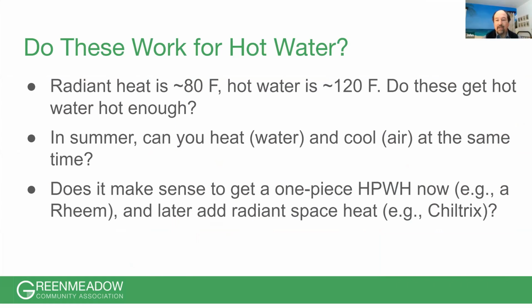Okay, yeah, so we've had to learn how to do this properly as an industry as far as doing domestic hot water from a heat pump. The Chiltrix unit, this is a case where you do have to match the Chiltrix to its indirect water heater. It's especially designed for that unit, with large water capacity, very low pressure drop, and a massive amount of heat exchanger. The other types of heat pumps that I've seen out there, like I think the SpacePak has just recently, over the last month and a half, figured out how to do domestic hot water in the controls.